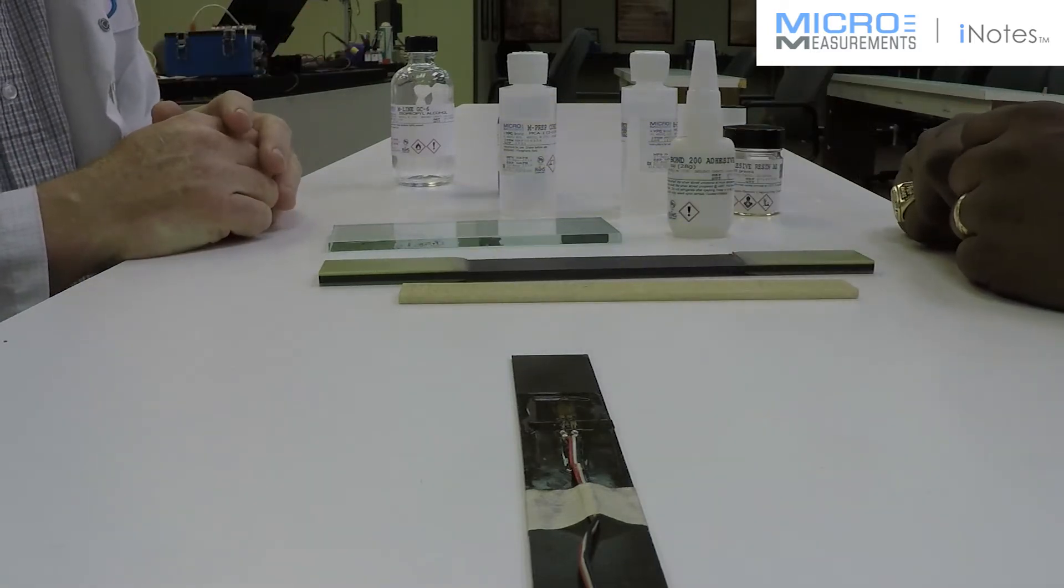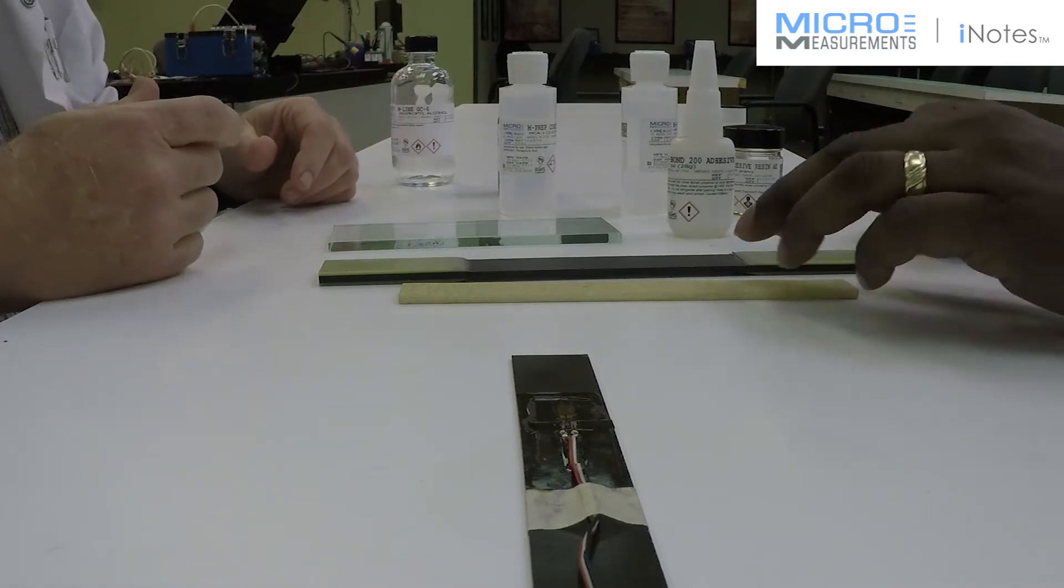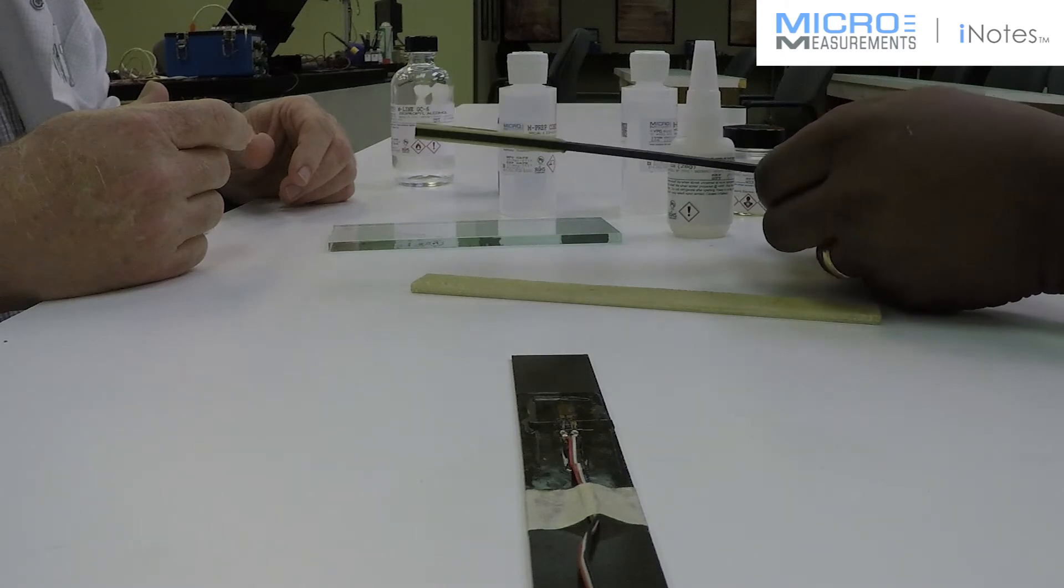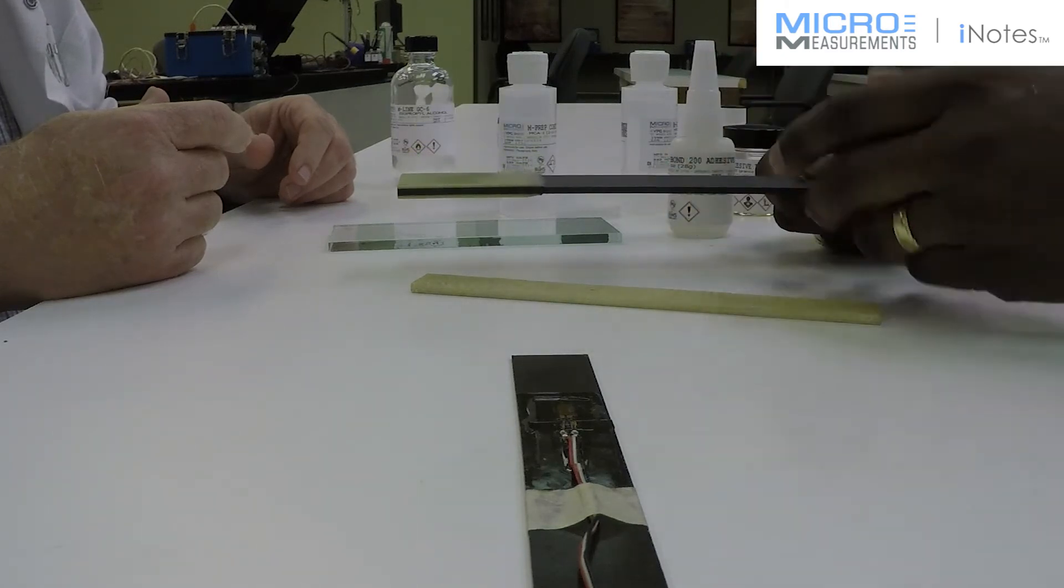What about the resistance of the strain gauge? 120, 350, 1000 ohm? What would be best? Since composite materials are generally poor heat sinks, you would generally go with a higher resistance gauge like a 350 ohm or greater in this application.